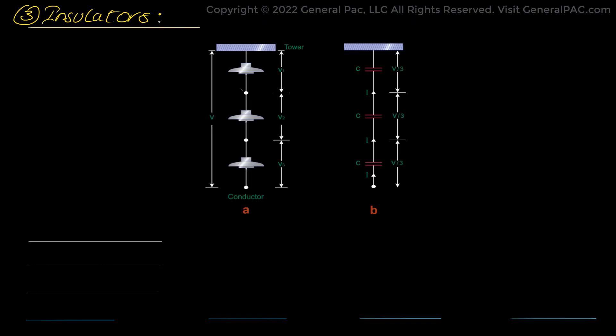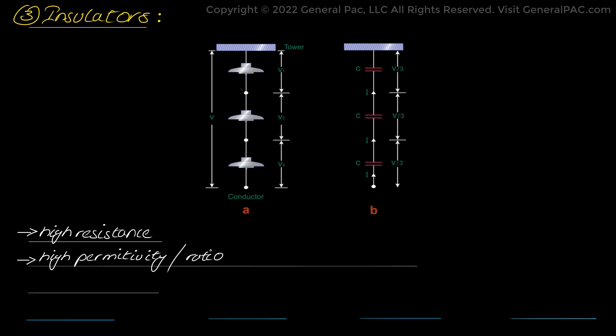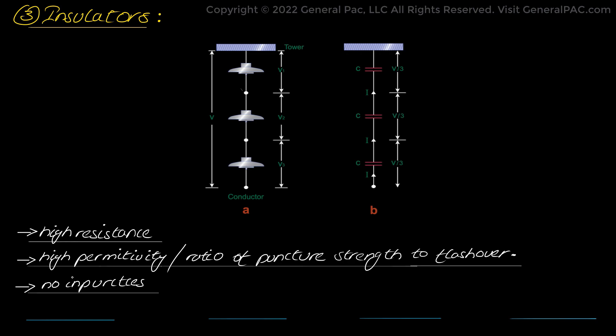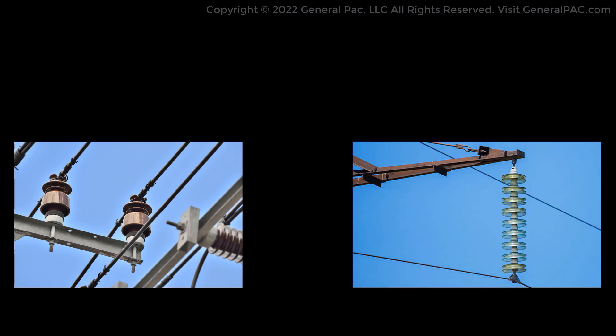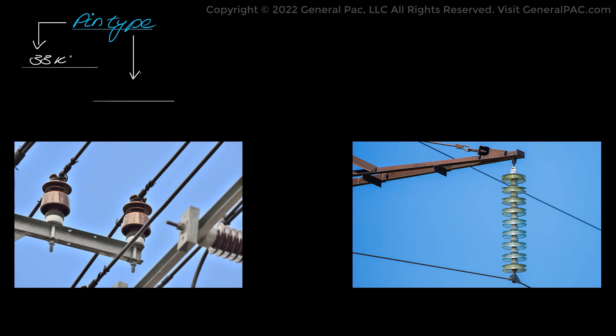Moving on to insulators — current from the line conductor should not flow to the ground through the line support. So it is imperative to provide insulation between the conductor and the line support. Insulators are used to provide that insulation to prevent leakage current. They should have high resistance, high relative permittivity in order to avoid leakage current, be free from impurities, and have a high ratio of puncture strength to flashover, which is a safety factor. Porcelain is the most commonly used material for insulators, but steatite, glass, and certain special composite materials could also be used. The most widely used types include pin type and suspension type, both made from glass and porcelain. Pin types are used for voltages up to 33 kV, after which suspension types are preferred.